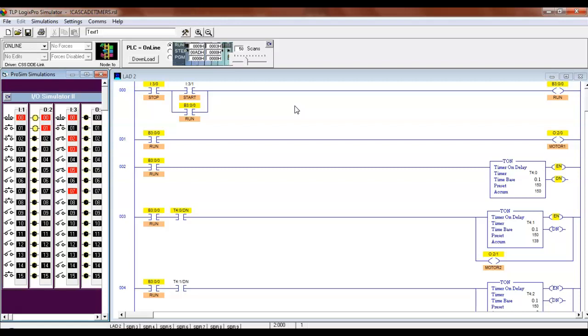So we use cascade timers to exceed the 32,768, right? So I could set this to 32,767. Then I could set this to 32,767. Then when this is true, it starts this timer, and then basically I would trigger whatever I wanted to trigger after the last time. And usually we wouldn't use 32,760. We usually use even numbers to make them easier to figure.